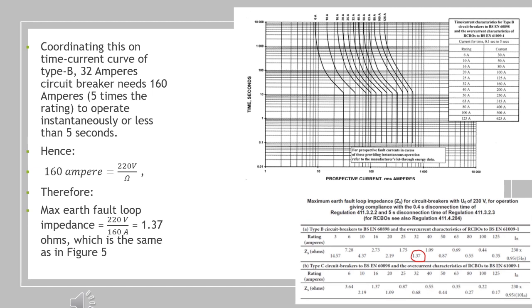The time and current characteristics of a type B circuit breaker are shown on the upper right. For the purpose of illustration, a 32 ampere circuit breaker will be used as an example. The chart in logarithmic scale says that 160 amperes, or 5 times the rating, is needed to instantaneously trip the circuit breaker from 0.1 to 5 seconds. To achieve this tripping current, the IEC or BS 7671 defines the maximum earth fault impedance, and in this particular example, this is 1.37 ohms.